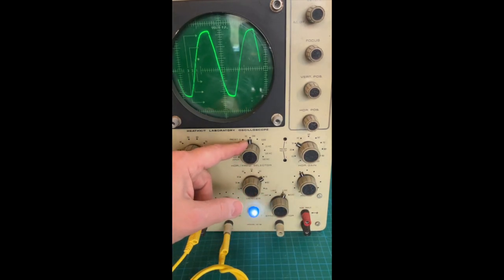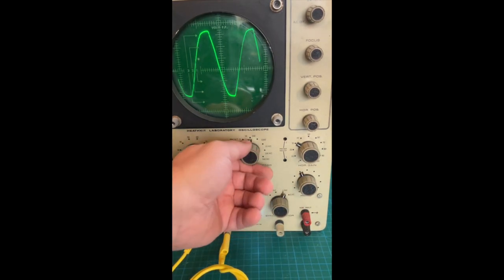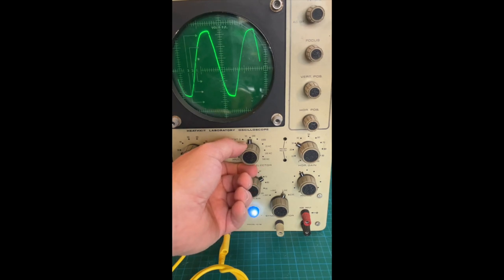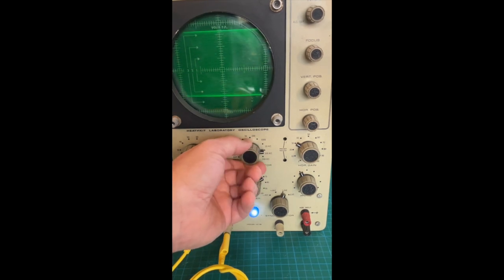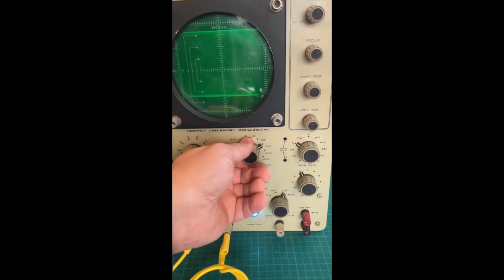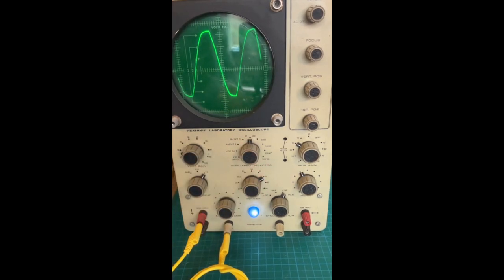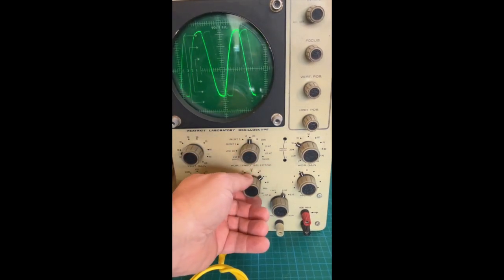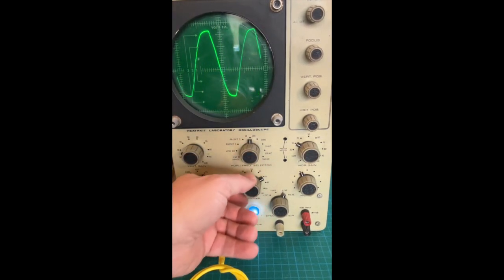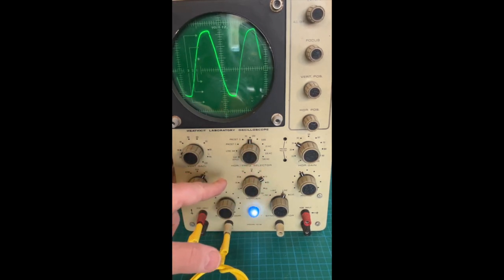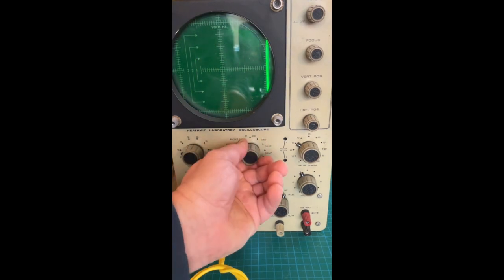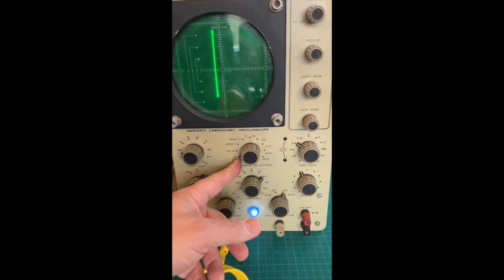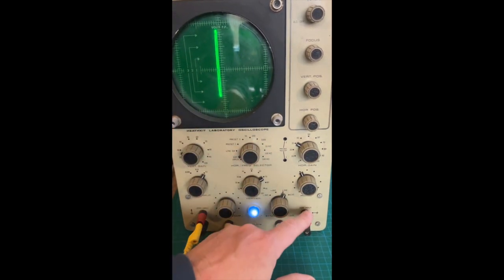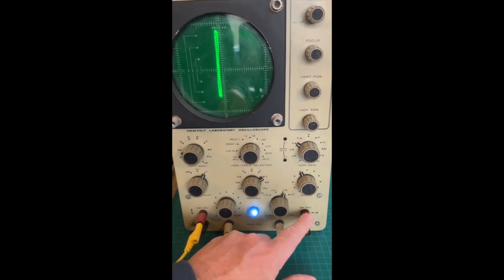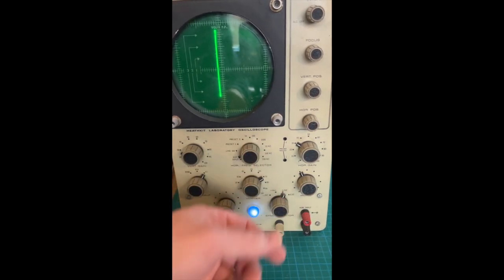This frequency selector has a lot of positions on it. There are 5 positions to select discrete frequencies, which you can fine tune here, sweep frequencies, but there are 4 other positions of this switch. Going from the bottom, you can select external input, and that's if you want to go into XY mode, you connect something here.